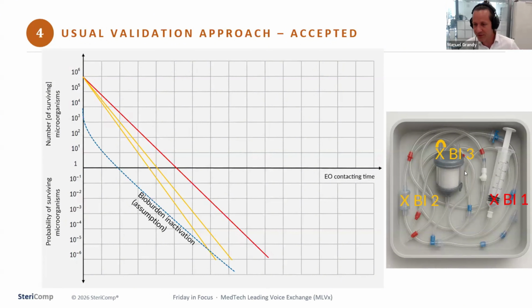And now the bioburden behaves differently. The bioburden is the microorganisms you have every day in your production. And here you have, first of all, it's not in a certain position. It's distributed in the whole set. And second, you have different kinds of microorganisms on it. So the easy-to-kill microorganisms, at the easy-to-kill positions, will die off very fast. And then you will have such a kind of curve, okay? A tail, it's called. This is how bioburden inactivation behaves. So you could also do some tests and measure it, and we assume now for this set this kind of bioburden inactivation. So now what you would do first in this usual validation approach is a so-called sublethal cycle, okay?